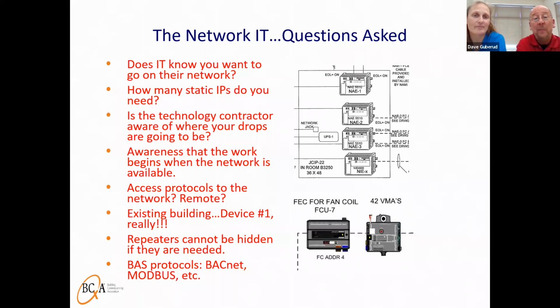And then, how many static IPs do you need? That engineer way in the beginning is just making an assumption of potentially how many are needed. Maybe he might be talking to the basis of design control contractor, but more often than not, he's just kind of throwing darts at it, if you will. And control contractors, more and more, we're seeing that they have IP-based controllers, and they're saying, wow, if I put this on the network, that's less wiring that I need to do. And all of a sudden we're up to like 8, 9, 10 or more IP drops. Number one, we're going to have to get static IP addresses for them. And to the next bullet point, the technology contractor is likely going to want to get paid for those 10 drops, because he probably just had one circle with one T potentially saying here.